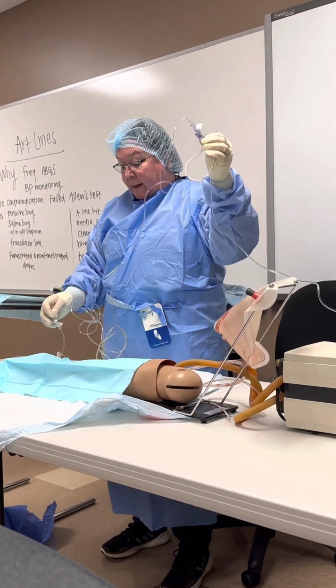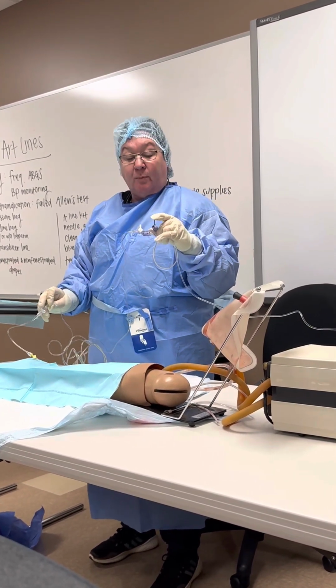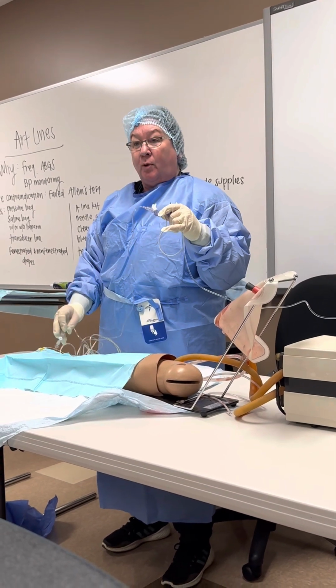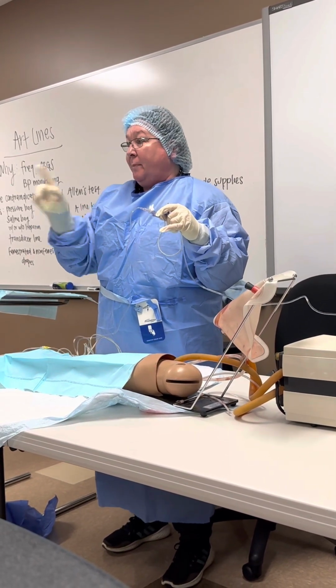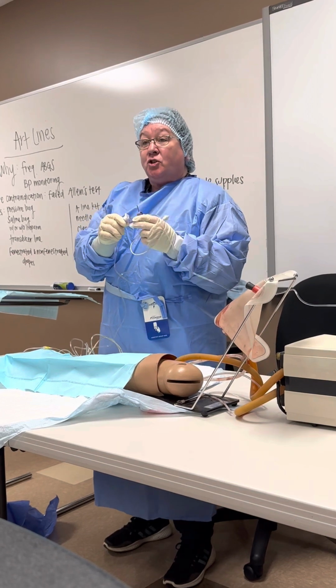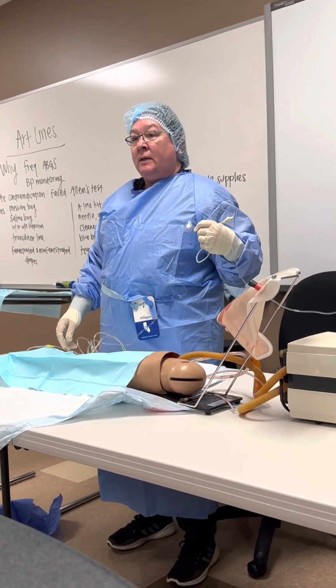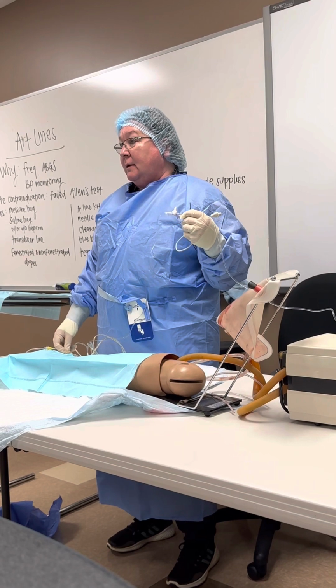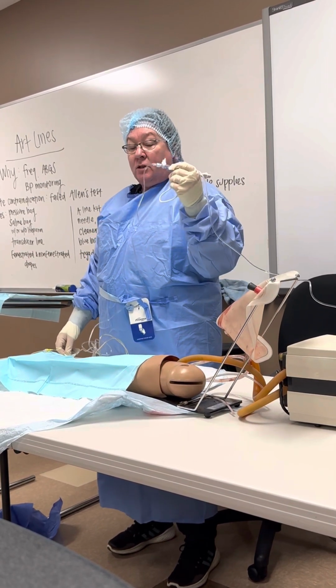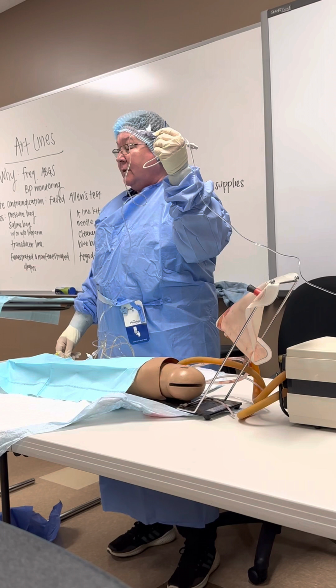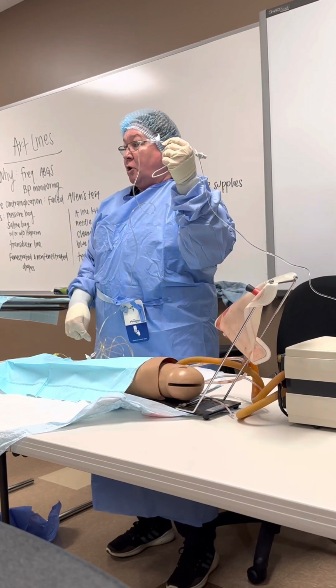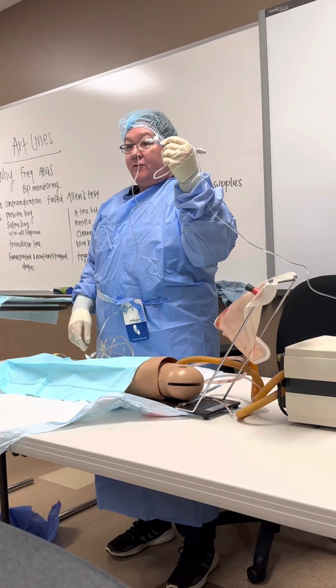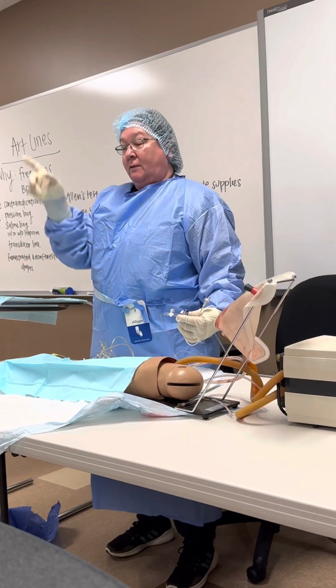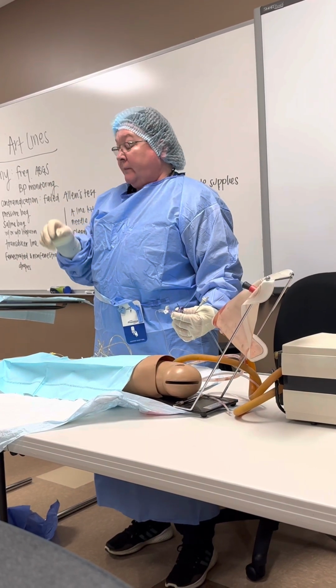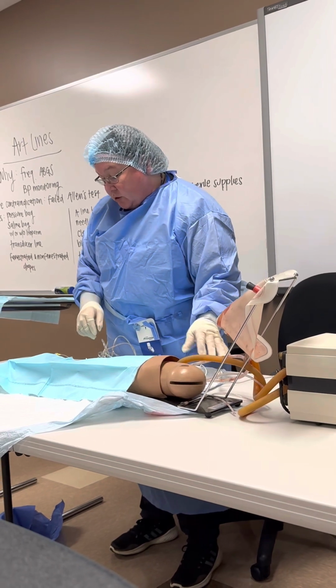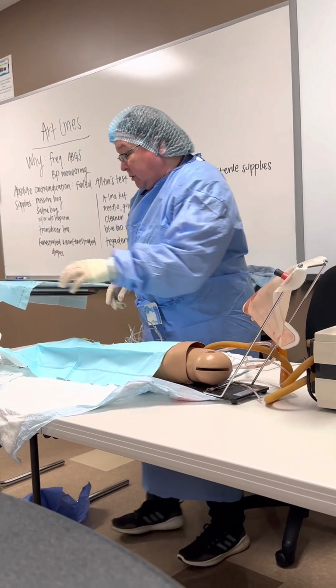When it's running and open, the stopcocks are gonna be pointed off to the port so it can have an open line. The transducer has to be at the level of the heart or you will not get an accurate reading. If the port is higher than the heart, the pressure will read lower, so they're inverse. If the port is lower than the heart, then they'll read higher, okay? So I'll show you how to draw from there in a minute. I wanna show you the other way.